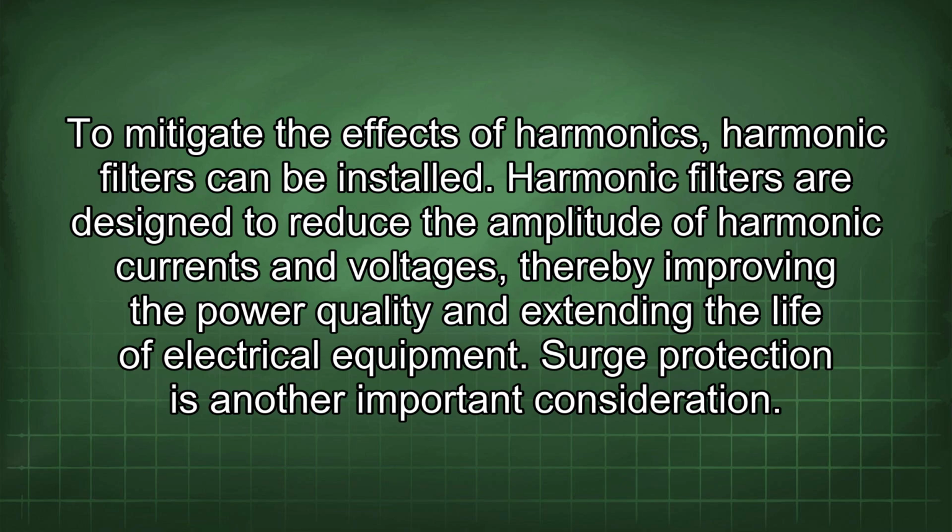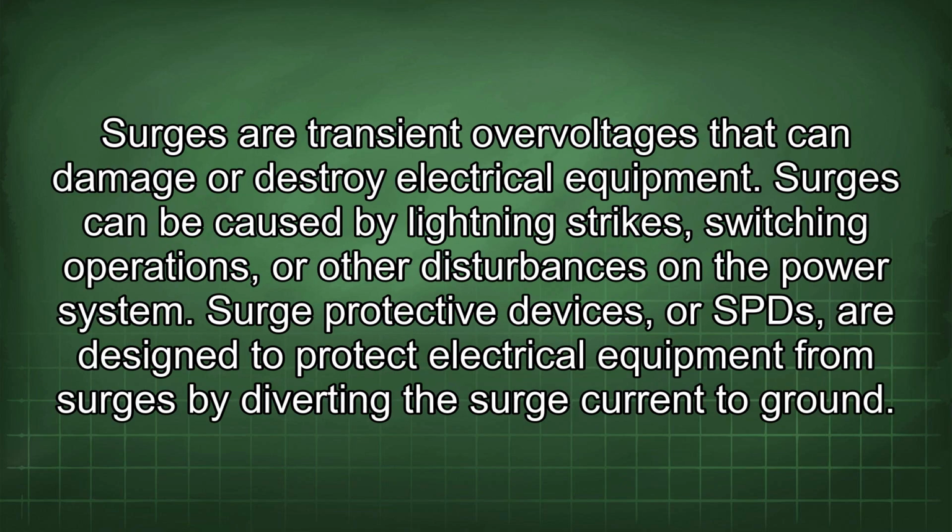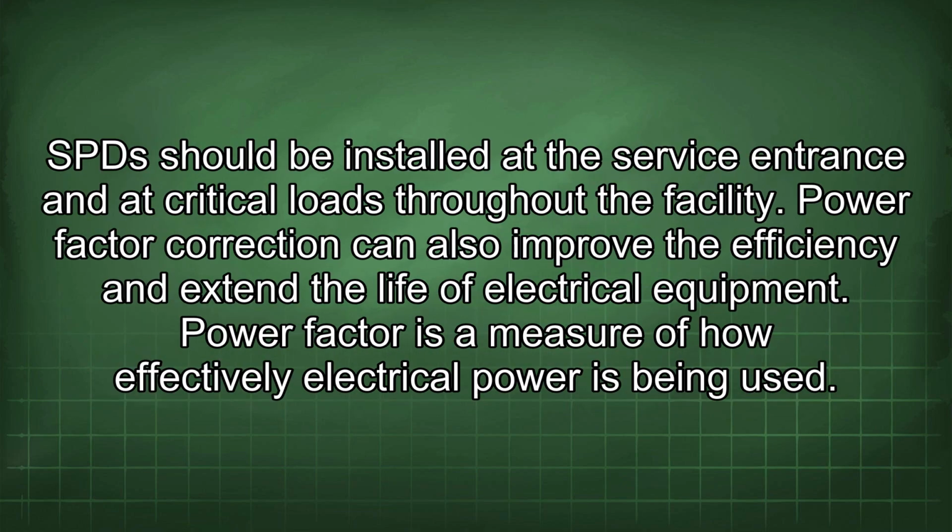Surge protection is another important consideration. Surges are transient overvoltages that can damage or destroy electrical equipment. Surges can be caused by lightning strikes, switching operations, or other disturbances on the power system. Surge protective devices, or SPDs, are designed to protect electrical equipment from surges by diverting the surge current to ground. SPDs should be installed at the service entrance and at critical loads throughout the facility.